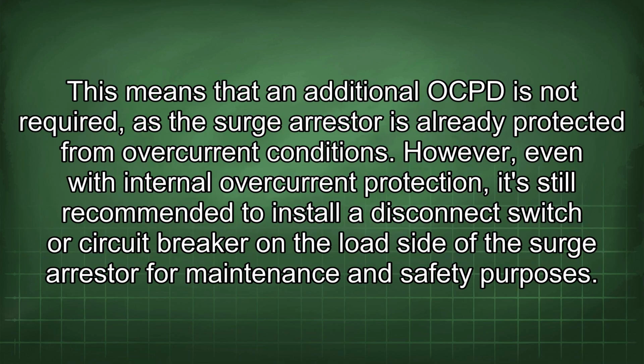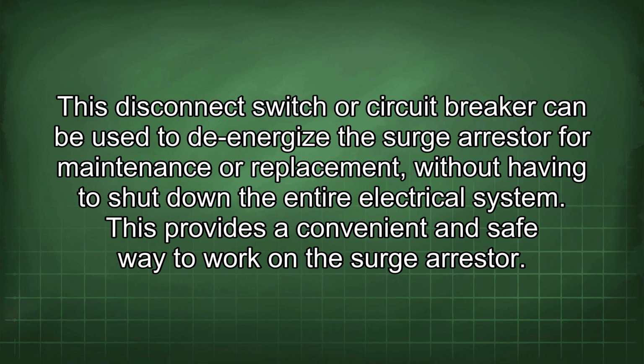This means that an additional OCPD is not required, as the surge arrestor is already protected from overcurrent conditions. However, even with internal overcurrent protection, it's still recommended to install a disconnect switch or circuit breaker on the load side of the surge arrestor for maintenance and safety purposes.